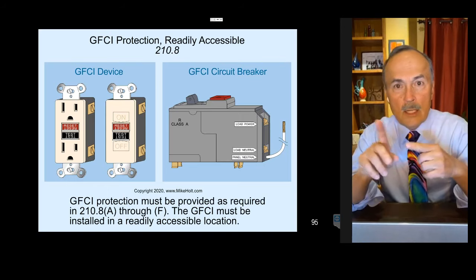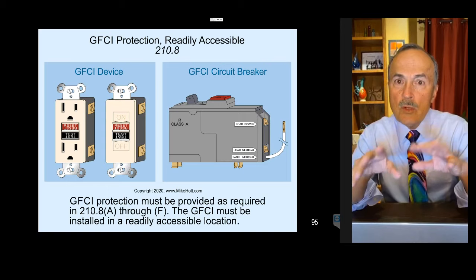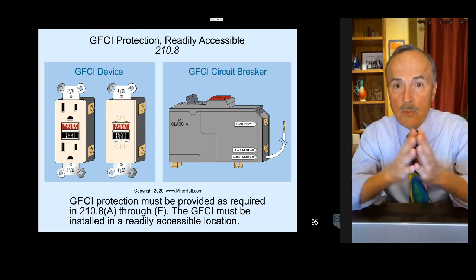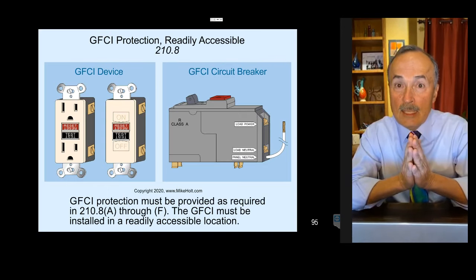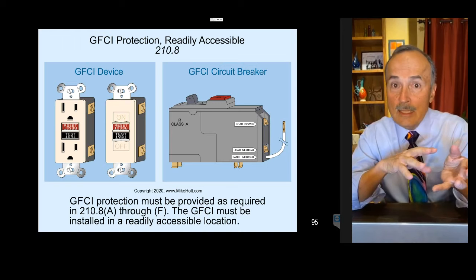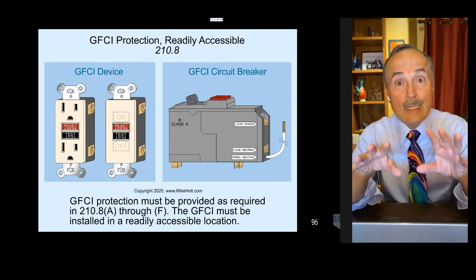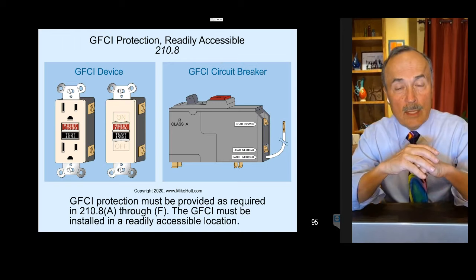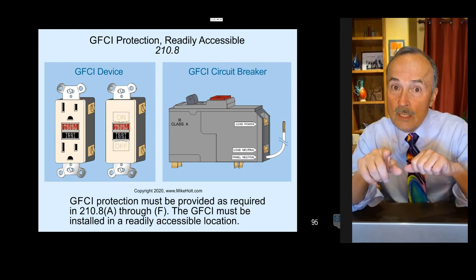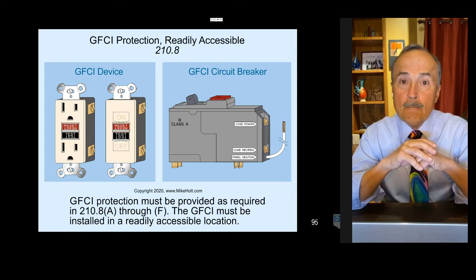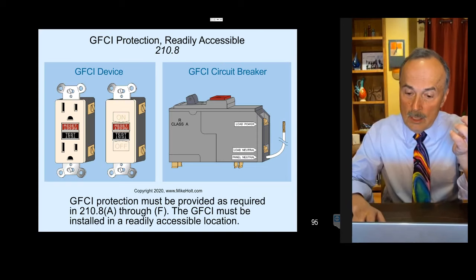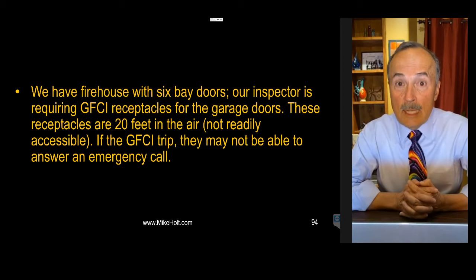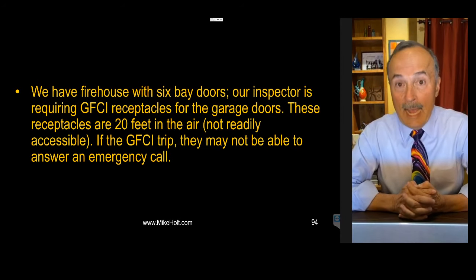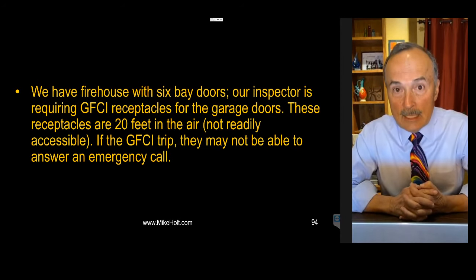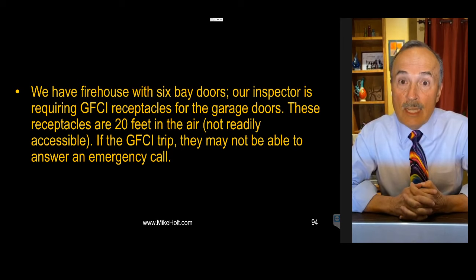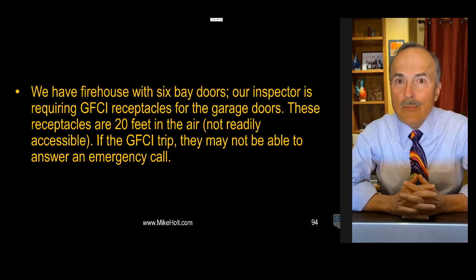And the logic is that you have AFCIs, GFCIs, you have smoke detectors, you have sensitive electronic equipment in a dwelling now that we're depending on to protect the occupants. Well, you get a transient, it goes inside and it wipes it all out. So it's requiring surge protection. So back to what we're talking about. GFCIs and AFCIs have an end of life. So don't think you're safe. Test the button, verify that it's working right. And because you have to always test that button, it needs to be readily accessible.